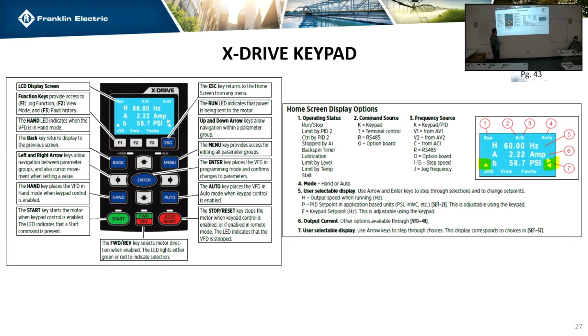If you are in local mode, you can hit the start button, the stop button, change forward and reverse. Again, if you want reverse, you're going to have to go in and make sure that the drive is enabled to go reverse.